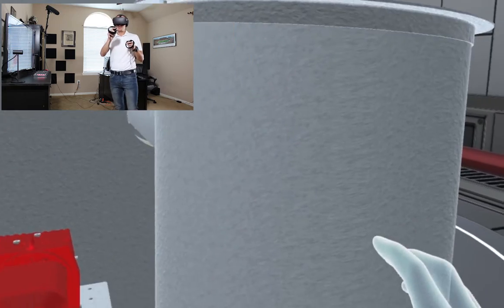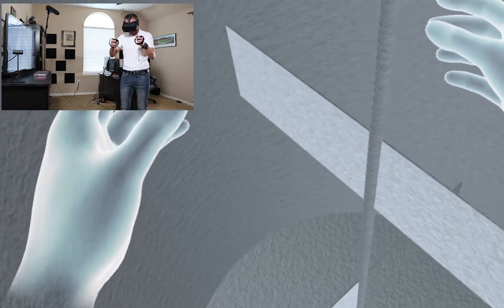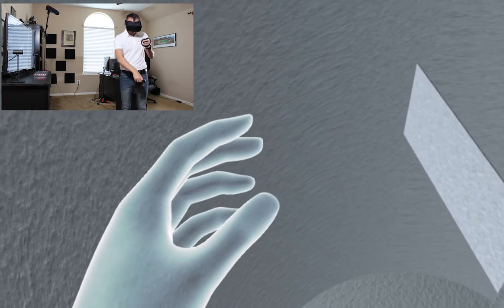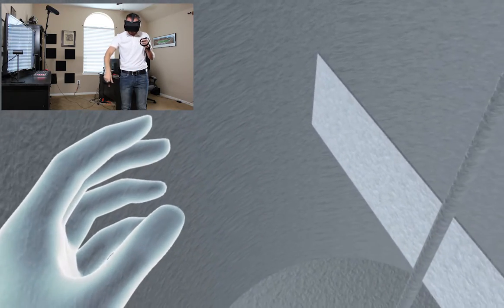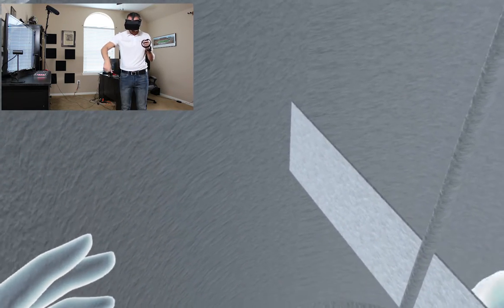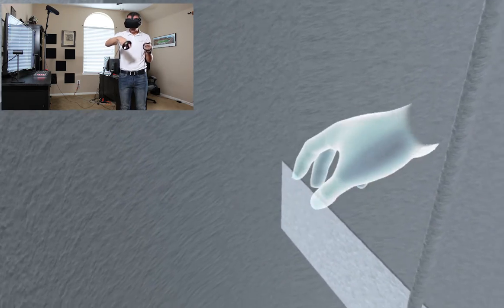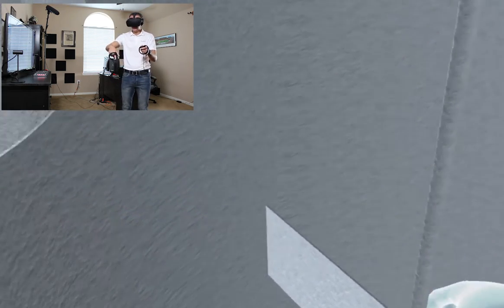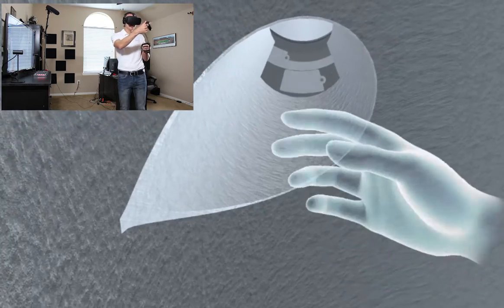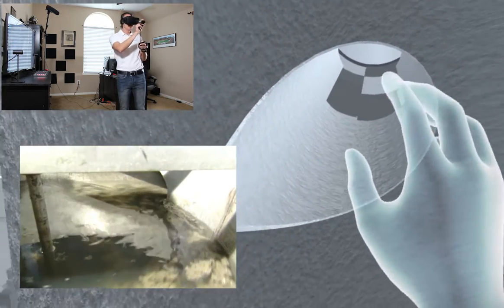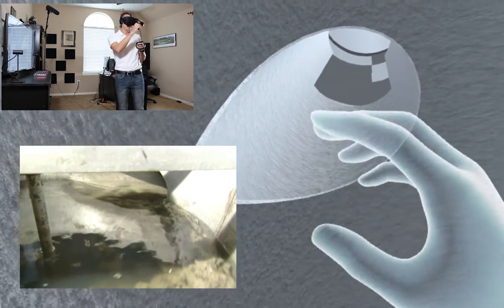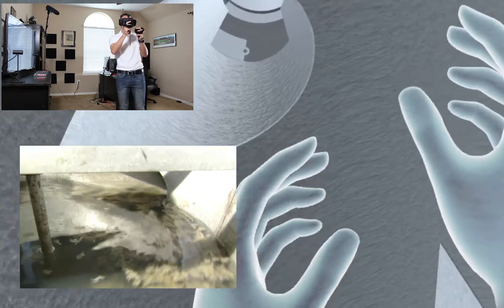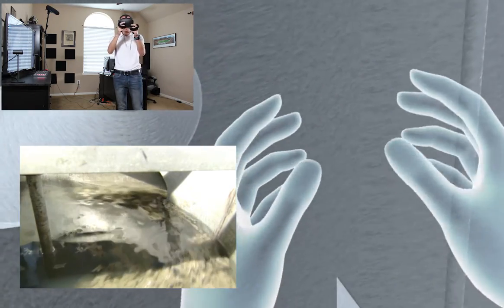So as we step into the floc tank, which we can in the virtual world here, now that we've induced that motion of that sludge, it comes up and swirls up through this floc tank and really gets a lot of the residence time, and it's pushed along with these baffles. And then when it's time to exit the tank, again, tangential exit.